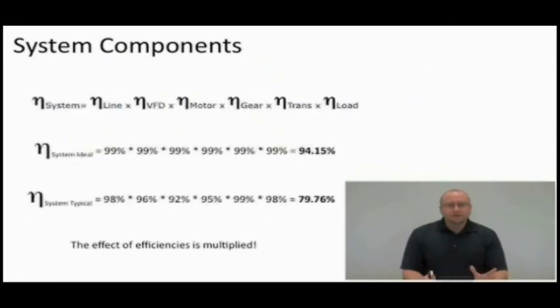Just for an example, if we looked at an ideal system where every component was 99% efficient, if we had our 6 components here, that they're all 99% efficient, when you multiply those together, our maximum efficiency is only 94.15%. That's throwing away over 5% of our power, almost 6% of our power, just to energy losses, to heat. And that's with an ideal system that's very efficient. And if we look at a typical system efficiency, and I selected some really good efficiency components here actually, multiplying these together, it's almost 80%, creeping up on 80% efficiency.